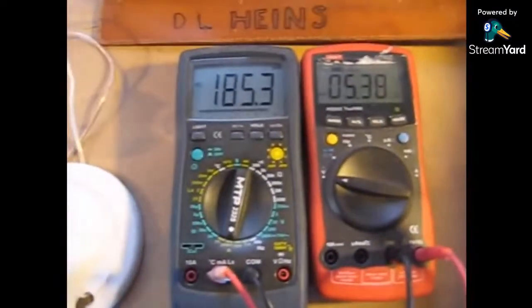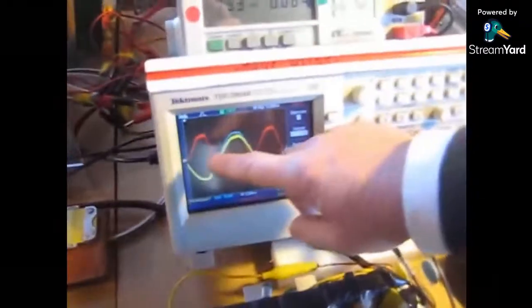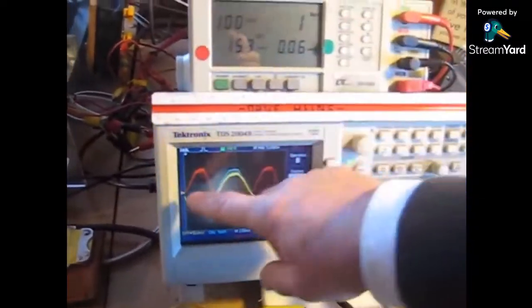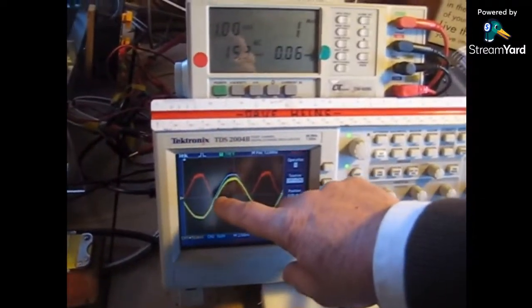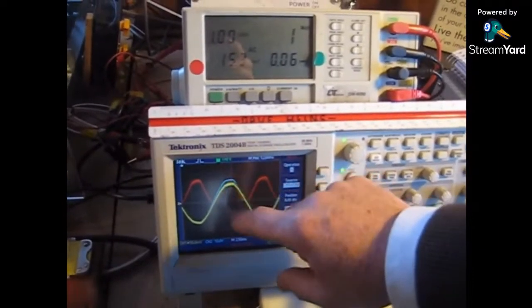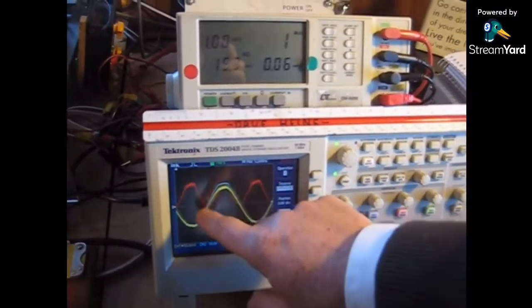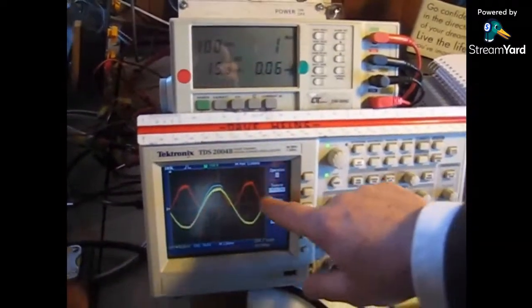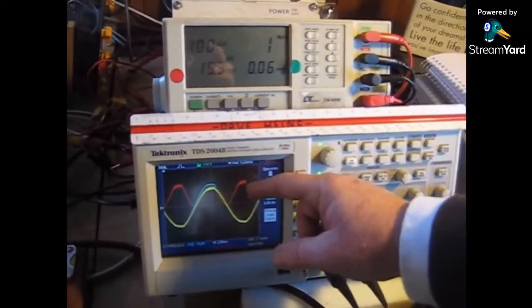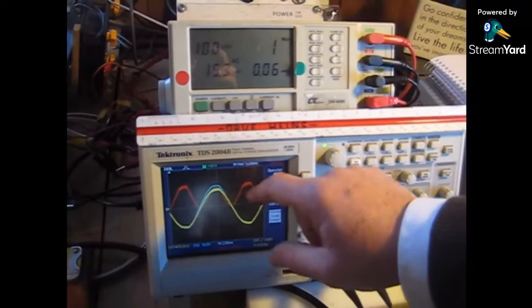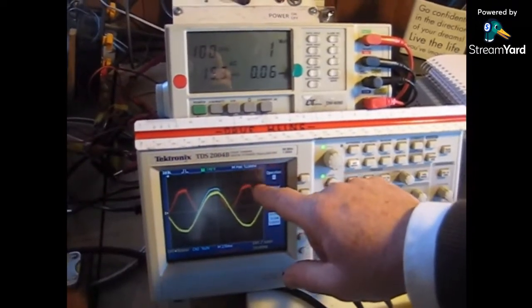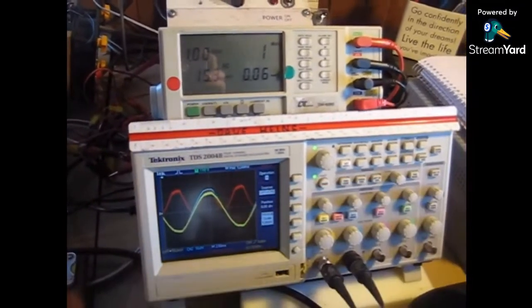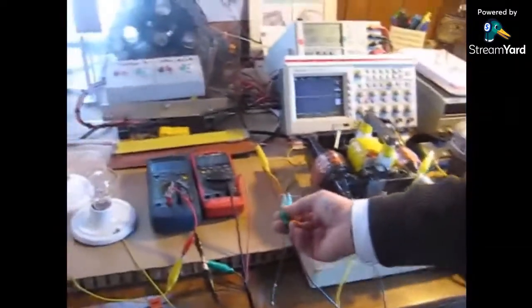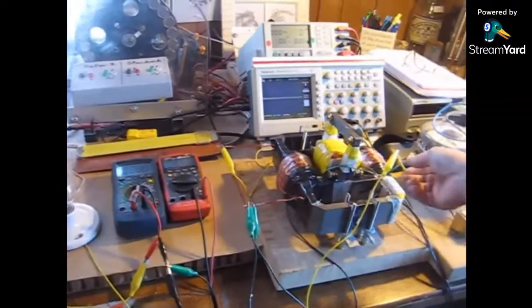And if we look at the sine wave, we can verify what the meter says, where the current and voltage are now in phase. The power sine wave is all above the middle line, denoting that all of the power that's being consumed in the primary is real power and that the power factor is 1. So now I'll put it back on the bi-toroid again so we can have a quick check here.